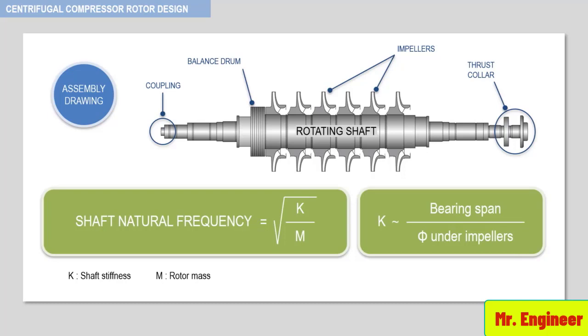Here, the bearing span is the distance between bearing centers. Now, an interesting rule of thumb is that dynamic compressor rotors with stable vibration characteristics usually have a K value higher than 10.